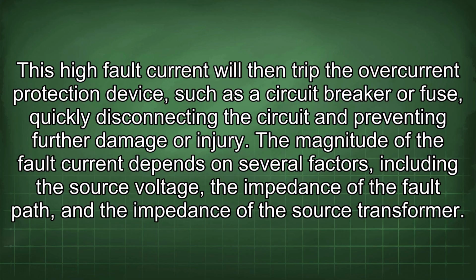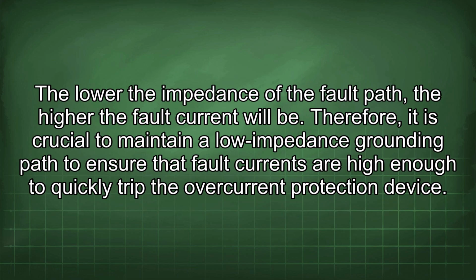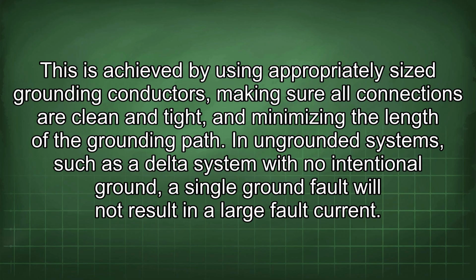The magnitude of the fault current depends on several factors, including the source voltage, the impedance of the fault path, and the impedance of the source transformer. The lower the impedance of the fault path, the higher the fault current will be. Therefore, it is crucial to maintain a low impedance grounding path to ensure that fault currents are high enough to quickly trip the overcurrent protection device. This is achieved by using appropriately sized grounding conductors, making sure all connections are clean and tight, and minimizing the length of the grounding path.